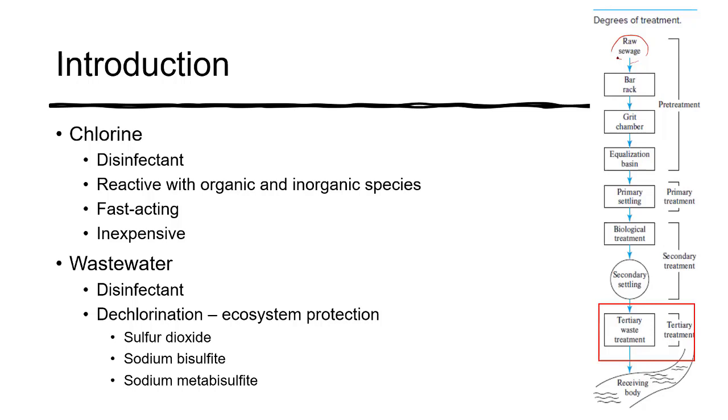And then from there, it goes into a grit chamber, and that's where the finer material, about the size of coffee grinds, is removed. Any sand particles, any coffee grinds, eggshells, they get removed in the grit chamber. This is predominantly inorganic, but there is some organic material. In some cases, there's an equalization basin to both equalize the strength of the wastewater and also the flow. And then into a primary settler, where there's about 60% removal of suspended solids, about 30% removal of the BOD.